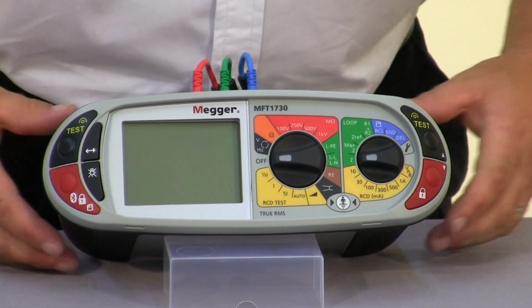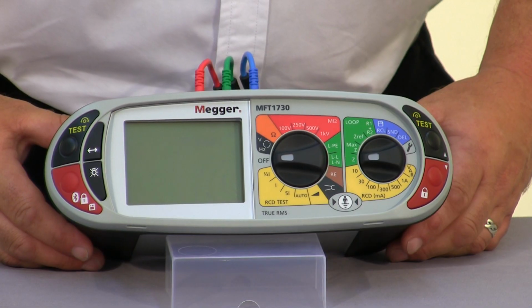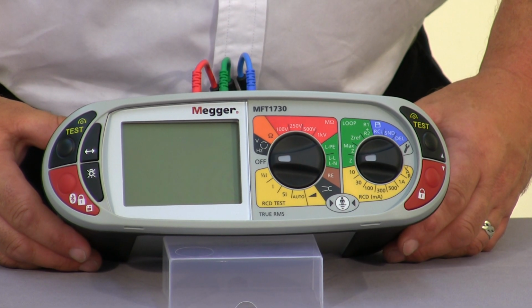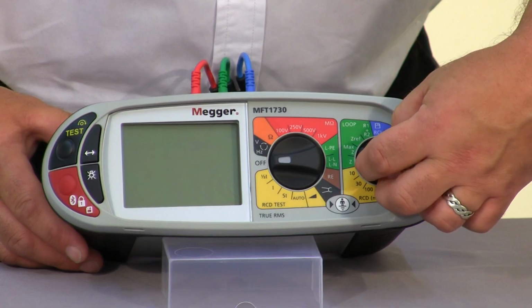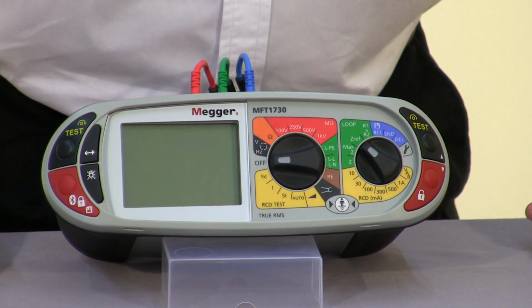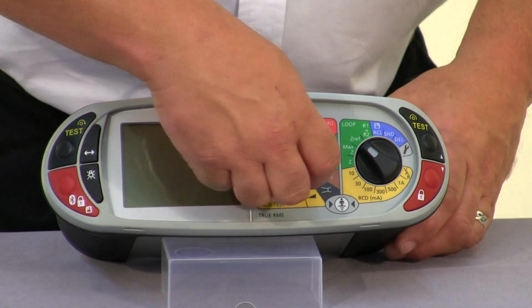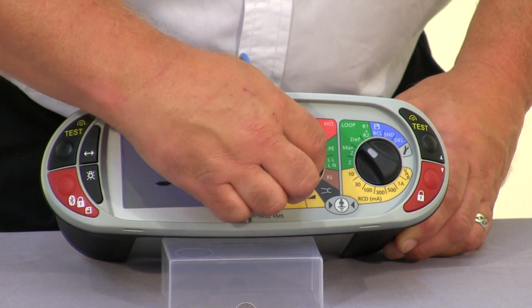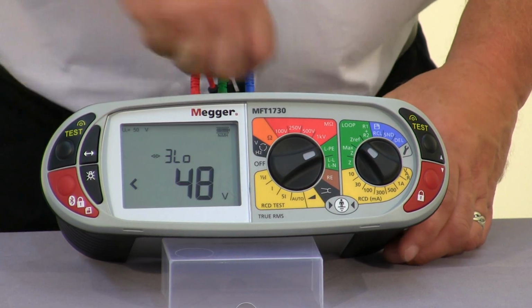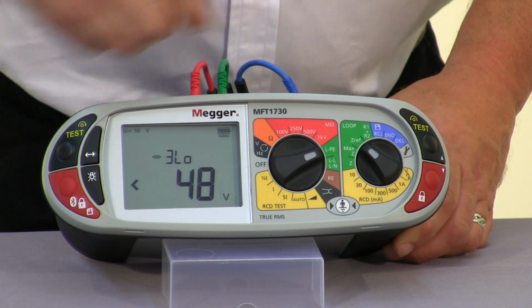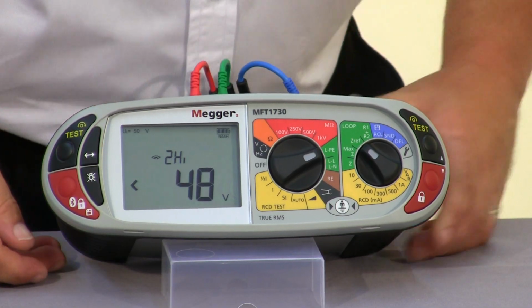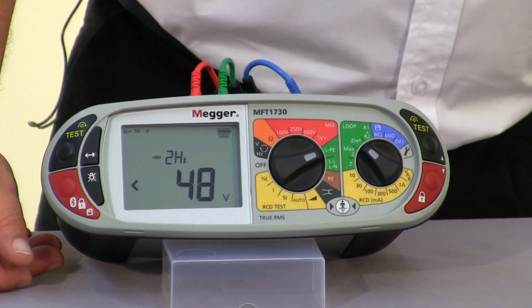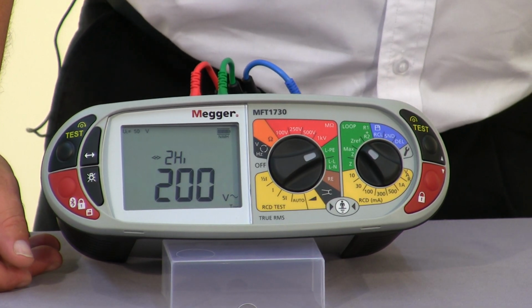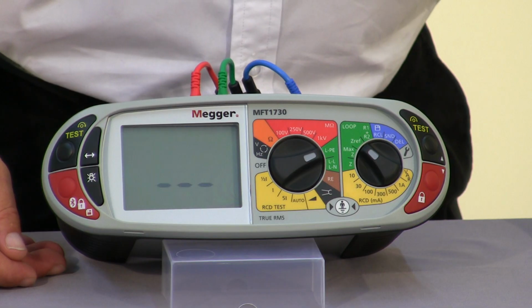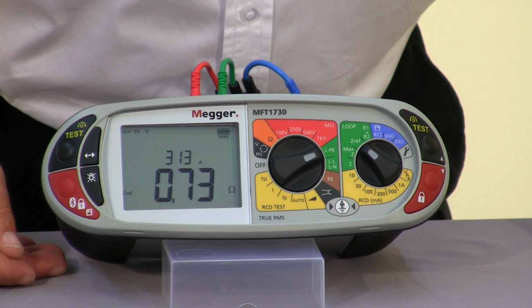Okay, and finally, on loop impedance testing, we'll look at the ZREF and R1, R2 test. The ZREF is actually our ZE, so it's a two-wire high current test that we do at the main incomer. So selecting a two-wire test, so on the function key, we apply to the circuit. The unit will auto detect and start the test, and we have a reading of 0.73 of an ohm.